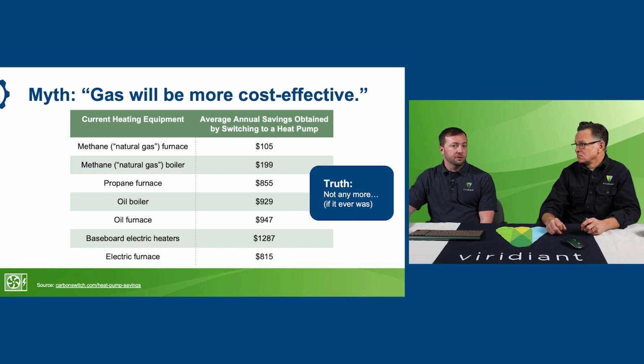Today you can find very high efficiency heat pumps. We're talking about an HSPF, the heating efficiency, over 12, and a SEER over 26, compared to historically an HSPF around 7 and a SEER around 10. And the COP numbers that you showed earlier help to tell that story as well about how efficient they are. At today's gas, propane, and oil prices, these high-performance heat pumps are going to be much easier on your wallet. Note that these are national averages that you're seeing in the table here. Local prices for electricity and various fuels will vary, but the equipment choices are the same nationwide.